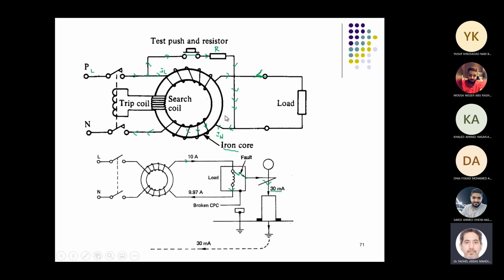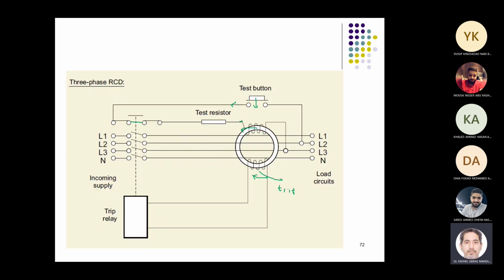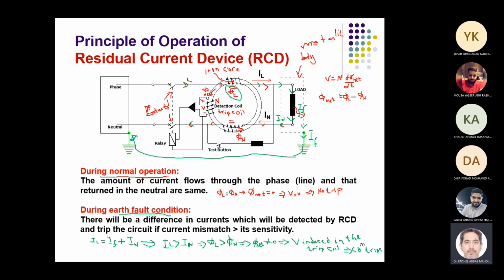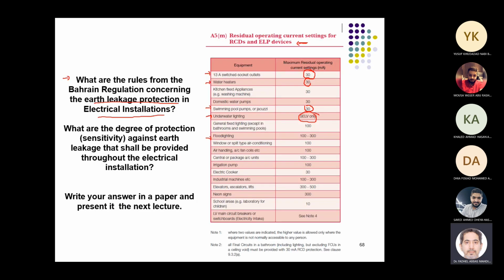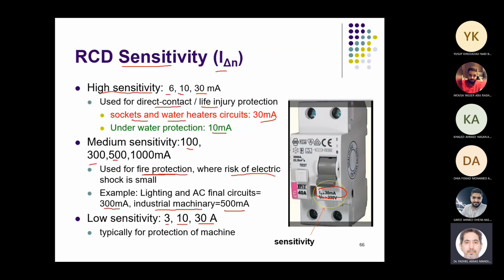So all of this is related to low voltage. They look like this for a three-phase, and they look like this, and they have sensitivity. It is written like I delta N 30 milliampere, which means if there is a difference in current between line and neutral, or if it's a single phase, of 30 milliampere, it will trip instantaneously. But there are different sensitivities. We have 30, 300 milliampere, and so forth.